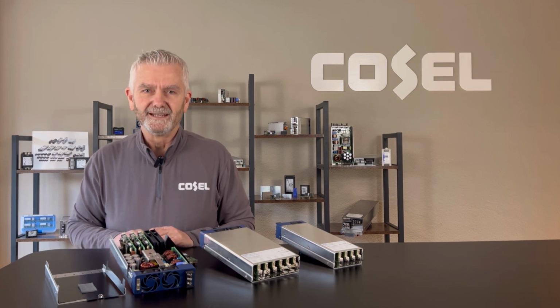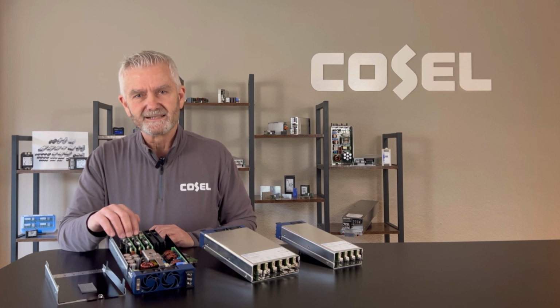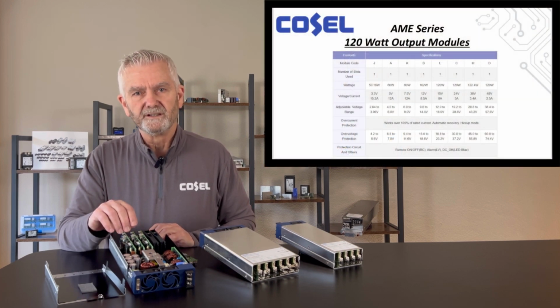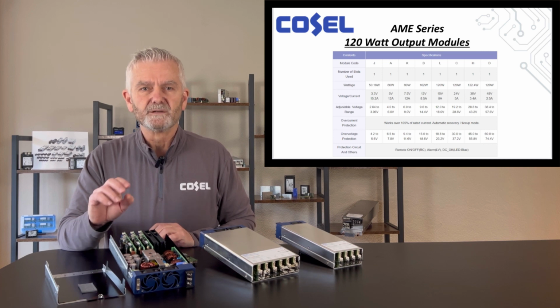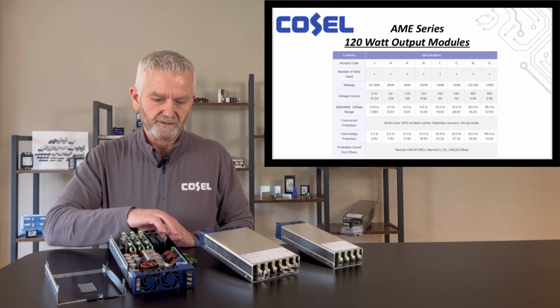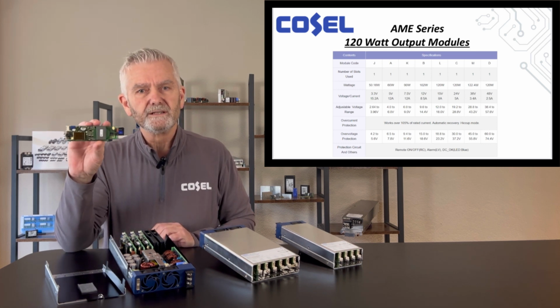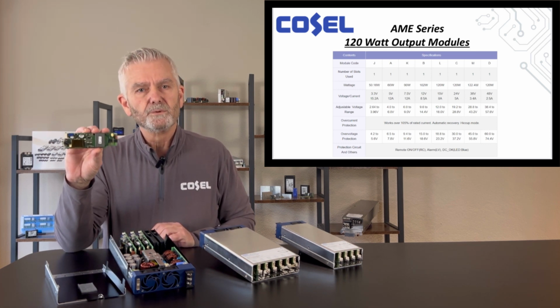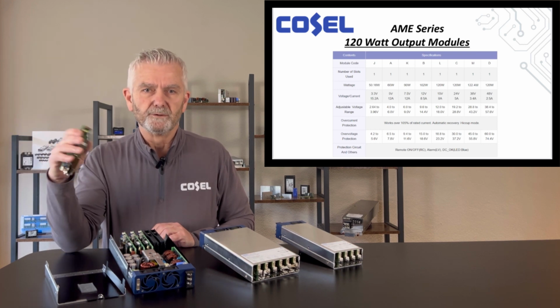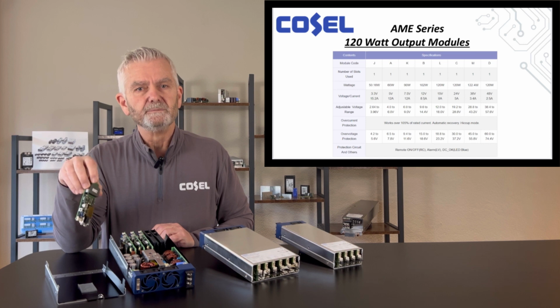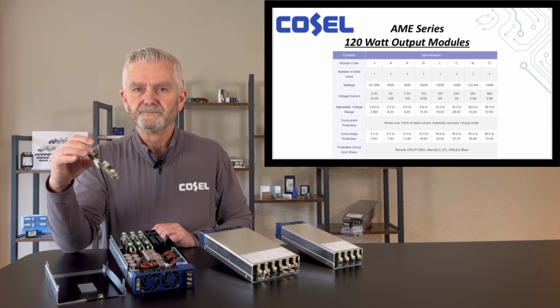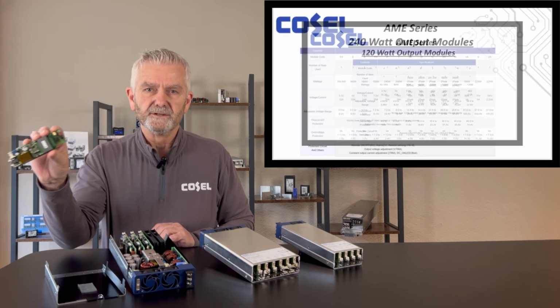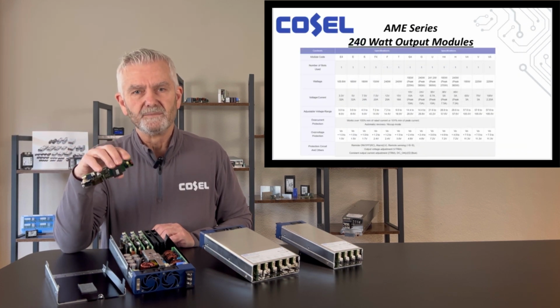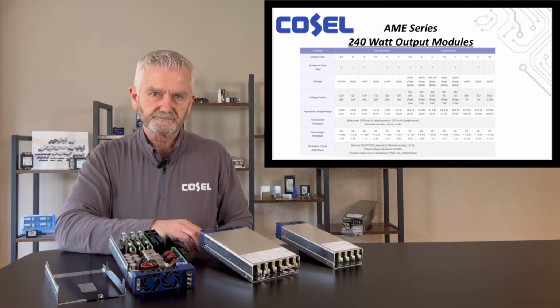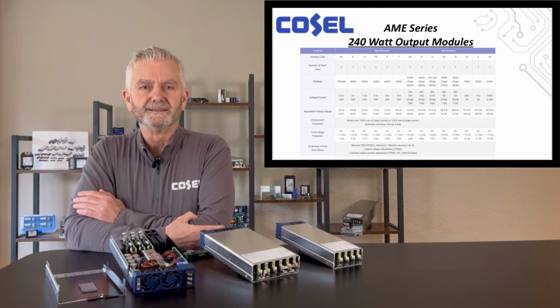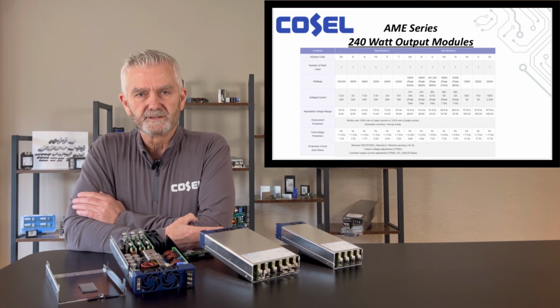Now let's delve into the heart of the AME series, with multiple independent isolated output modules, each with its own configurable settings. The AME series offers unprecedented flexibility in voltage and current options. There are 23 single slot output modules with output voltages from 3.3 to 100 volts. These outputs collectively can be trimmed from 3 volts to 105 volts. There are 120 watt and 240 watt single output, single slot modules, and 1 dual output module. The dual outputs can trim independently from 5 volts to 25.2 volts.